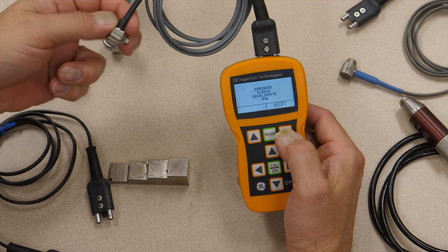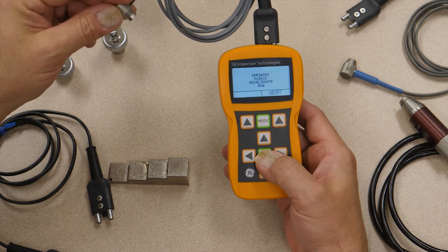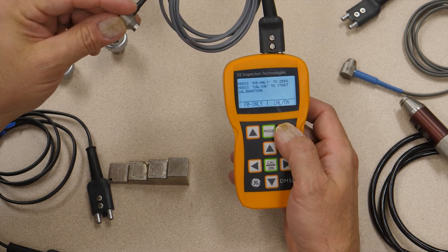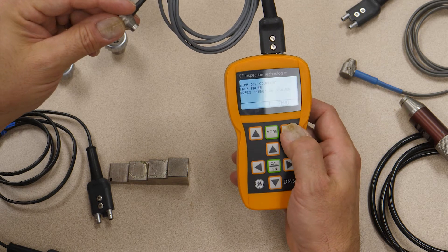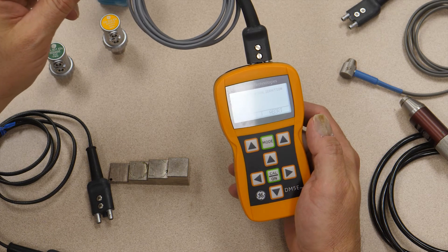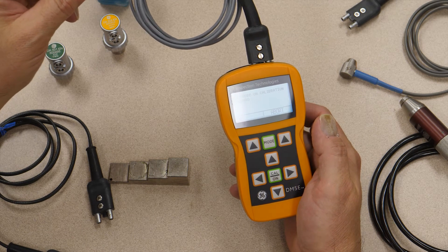All right, so we just plugged on a new probe. We need to run through a calibration. I'm going to do a full calibration. I zero the probe. And the DM5E typically uses auto zero, so it's pulsing and listening on each side of the probe right now as the probe is held in the air.